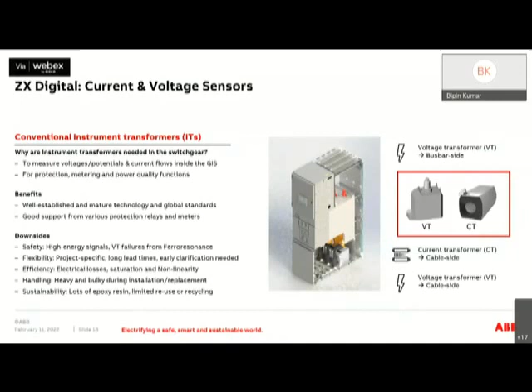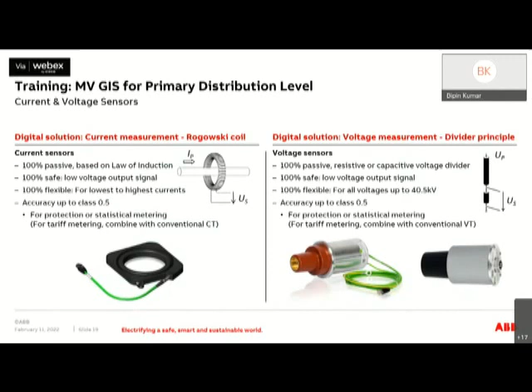And we have also done a typical sort of saving analysis in terms of giving a commercial nature to it. So we have compared a similar 14 panel board which are using sensors, and a 14 panel board which are using, let's say, conventional current and voltage transformers. Over 30 years of lifetime, they end up saving approximately 15 to 20 lakhs for a customer, only for a 14 panel board, because they practically do not have any windings, so they do not have any energy loss aspect to it.